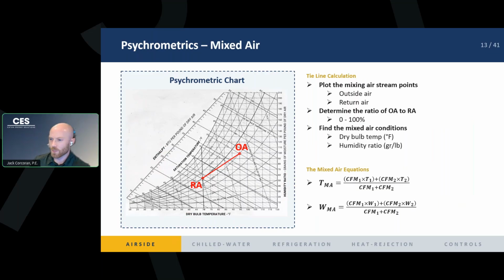Another important piece of information is our mixed air, right? And so we said there's two ways to deliver our air into the space, and one of them is mixing it with return air, right? So if you look at the chart here, RA is our return air, OA is our outside air. I plotted our 95-degree outside air along the bottom axis. The dry bulb is 95, and then if you look at the wet bulb, which is the diagonal lines on the left side, that's at 75. So our outside air is 95, 75. In New York, that's pretty close to the peak enthalpy day that you're going to achieve, and most of the time you'll be sizing your coils with that as the outside air temp and wet bulb. And then your return air is going to be somewhere in the 70 degrees and 50% relative humidity. I plotted those 2 points.